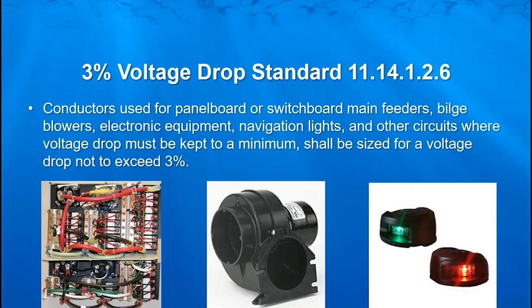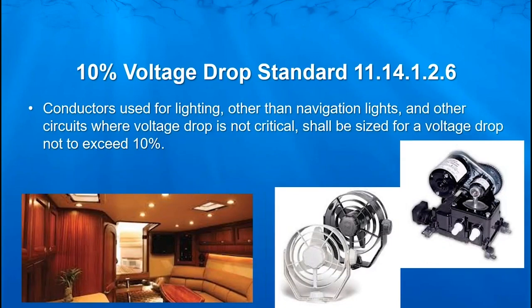Conductors used for panel board or switchboard feeders, bilge blowers, electronic equipment, navigation lights, and other circuits where voltage drop has got to be kept to a minimum — that wire shall be sized for a voltage drop not to exceed 3%. Conductors used for lighting other than nav lights and other circuits where voltage drop is not critical shall be sized for a voltage drop not to exceed 10%. Even for non-critical items, we don't want it to go over 10%, as 10% voltage drop for most electrical items is going to be an issue — it's just not going to work right.